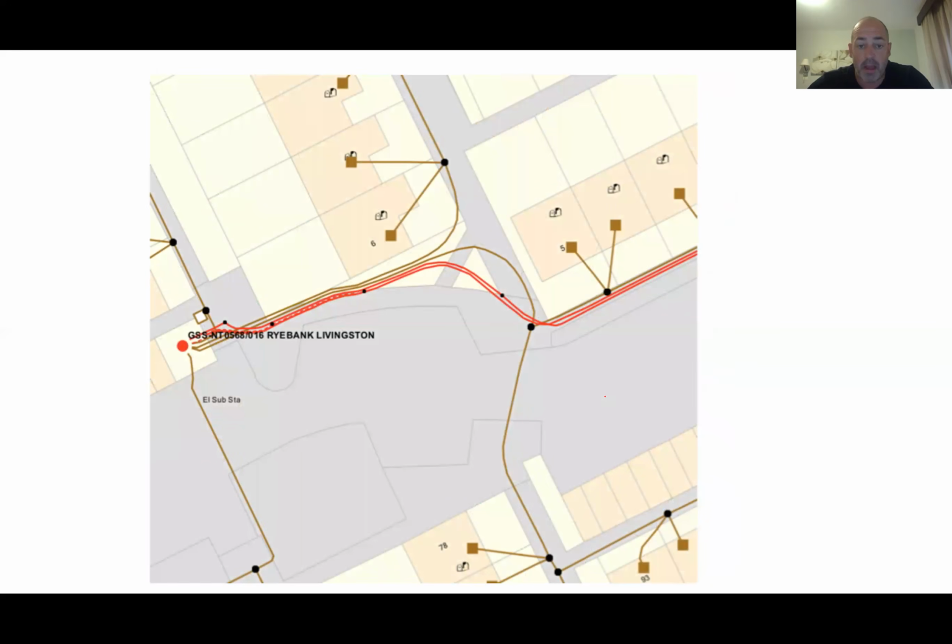Another little example, so back to Scottish Power, we have LV and HV in here. You can imagine the response you get from your locator on power in this area. But what we can do here is we can hook up here and get the majority signal on the top one, and then here and get that one. So again, we can use our plans to help us work out where we can put our transmitter signal and the best place to apply it.